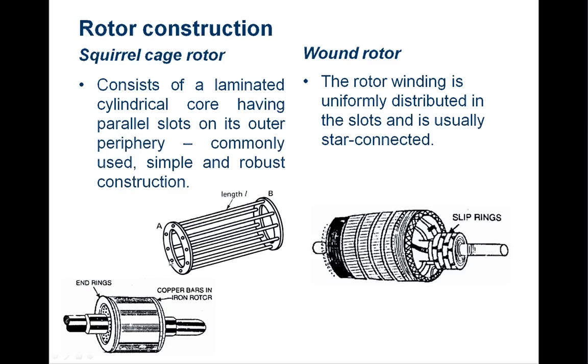It consists of a laminated cylindrical core having parallel slots in its outer periphery — a commonly used, simple, and robust construction. The copper bars are submerged inside the rotor iron, with short-circuiting rings on either side. That is the squirrel cage rotor.